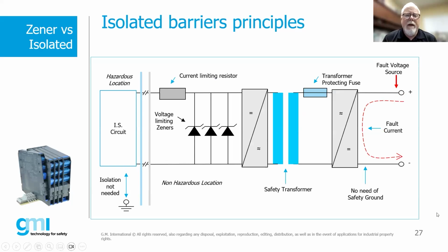When we look at an isolator or galvanically isolated barrier, in this case, we've introduced a safety transformer. As we mentioned, it could be an optocoupler, it could be some sort of transformer. This is actually built into the barrier itself. So this device does have to be loop powered in some way, shape, or form. We still have the Zener diodes, current limiting resistor, and the fuse. But in this case, if we have a fault condition coming down from, say, the controller, it's going to hit that transformer. And notice that we don't have to have a safety ground because we've eliminated that fault condition from entering into the hazardous area by the use of this transformer. So it's not a direct connection. It is using a transformer to transform the signal.